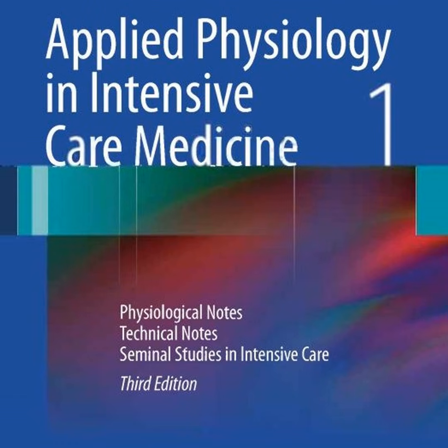It does. Now, in a controlled ventilation setting, we can measure this pretty reliably with an expiratory hold or pause. So when you apply that expiratory hold, what's physically happening that gives you a true reading? Well, the hold closes the expiratory port, so it completely eliminates flow. With no flow, there's no pressure gradient. So the airway pressure has time to equilibrate with the mean alveolar pressure. I see. And the difference between that newly measured pressure and the PEEP you set on the machine, that is your PEEP-I. And that total pressure is what the patient has to fight against to trigger the next breath. It dramatically increases their work of breathing.